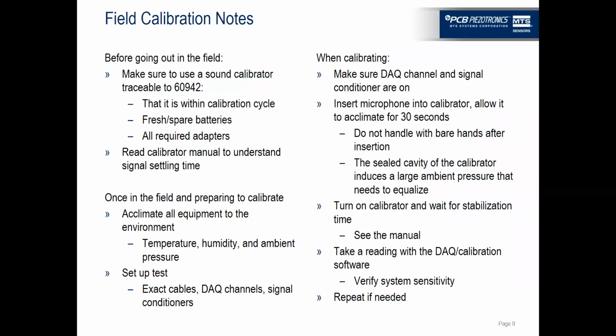It's a note here, I've had this question before. Can you damage a microphone by putting it into a sound calibrator? And my answer is, if the sound calibrator is designed well, no. I've never heard of any of the mainstream models of sound calibrators damaging a microphone just by inserting it. They should have enough of a leak path and enough volume on the inside that it won't damage or destroy the diaphragm of the microphone.